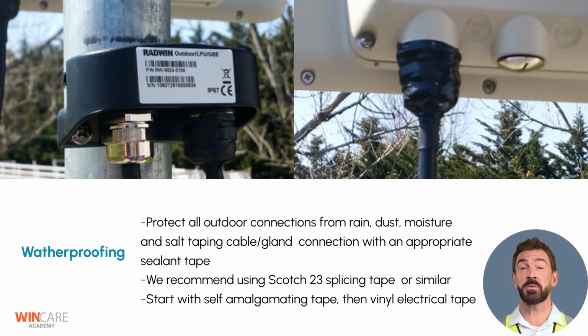To protect all outdoor connections from rain, dust, moisture, and salt, always seal every cable and gland connection using proper waterproofing tape. Begin with a layer of self-amalgamating tape, such as Scotch 23, to create a strong waterproof barrier. Then, apply vinyl electrical tape over it to protect against ultraviolet radiation and secure the seal in place. Use a moderate amount of material, not too much, not too little. Following this method ensures long-term protection and reliability of your outdoor installation.